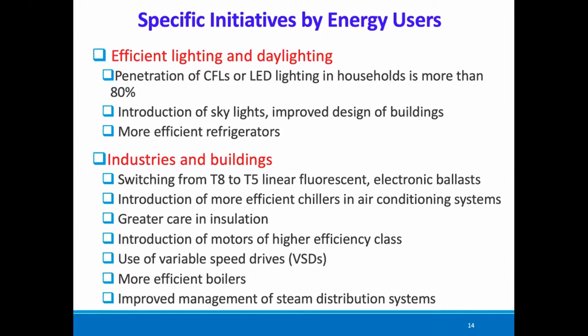The introduction of motors of higher efficiency classes is now increasingly common, where you could pay more and buy a motor which is 2% or 3% more efficient than the standard design. The use of variable speed drives is also common, since industrial drives require different speeds at different times depending on the production process. The age-old practice was to throttle the airflow or water flow, but the correct practice to save energy is to change the speed of the motor, so that energy is efficiently used and not wasted in the throttling process.